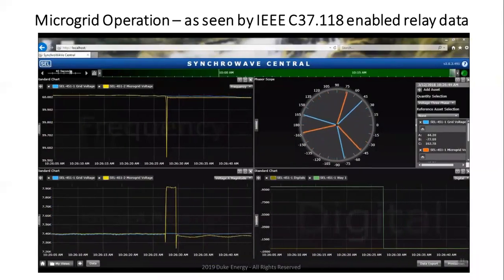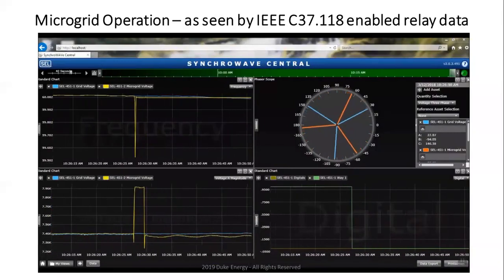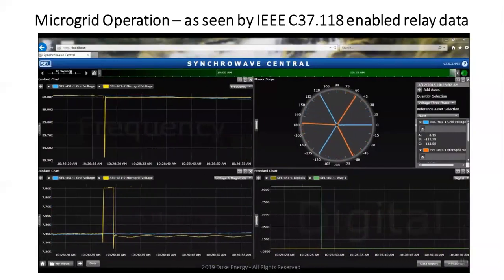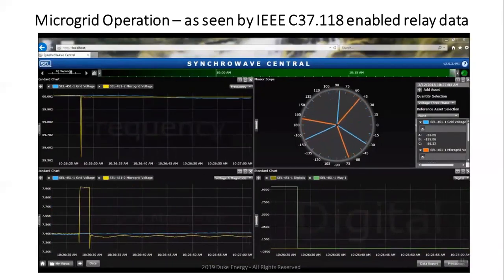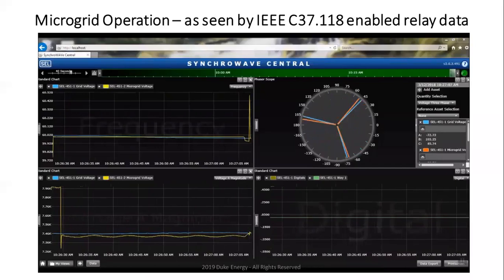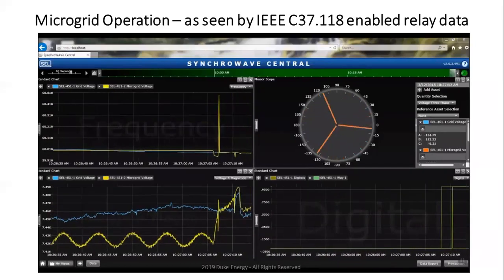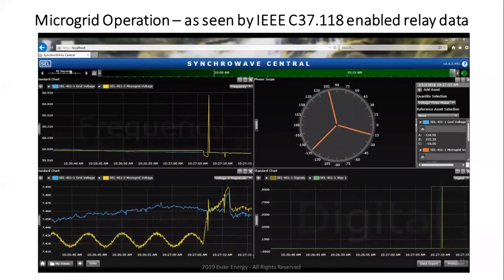You are going to see voltages on the left. You're going to see on the right how angle within the grid and angle with microgrid is not. And now you can see on the bottom, we issued the request to go back to the grid, and you can see immediately after, because the angles were really, really close, they closed within probably half a second or so. Typically, it's about 2 to 6 seconds. This is synchrophasor data, right? So everything that you see over here, you have one sample per cycle, right?